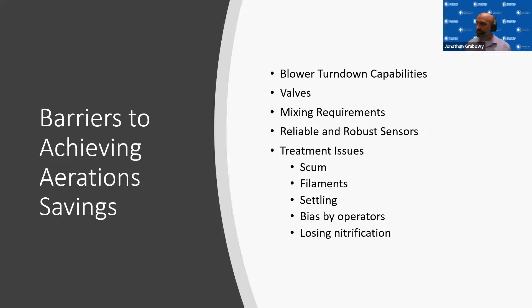So we did a couple tests. So if you could go to the next slide. We did an ammonia-based aeration control test at our Stickney plant in 2019. This was based off a process model that showed that we could get about a 32% savings in airflow using ammonia-based aeration control. Stickney has actuated valves, but we have very limited blower turn down.